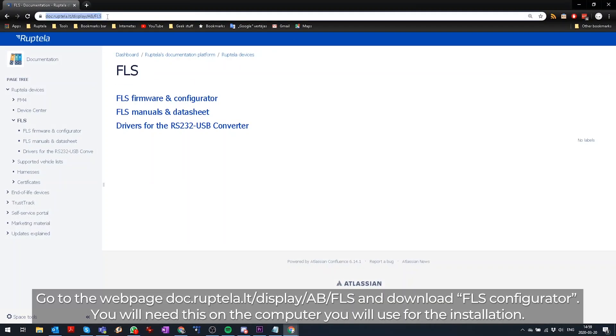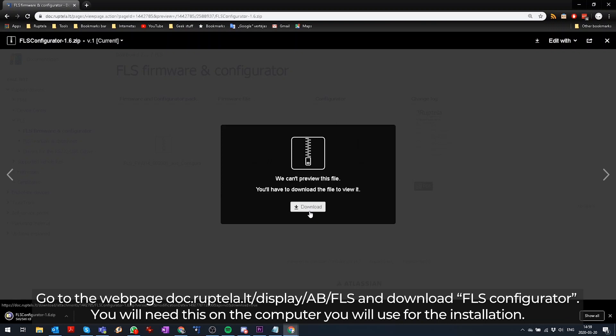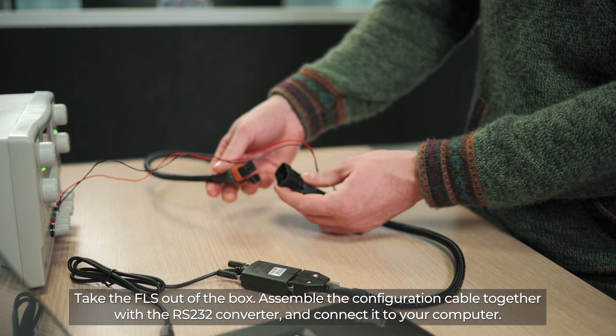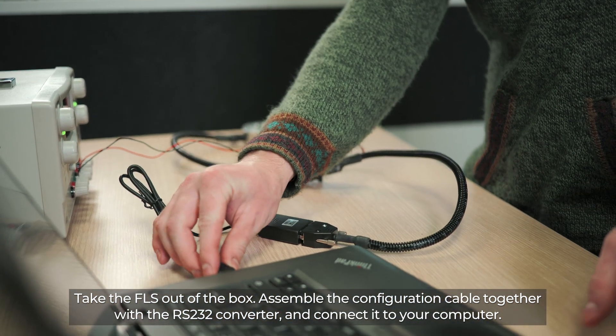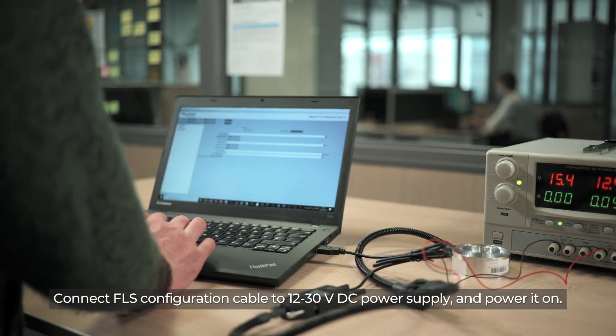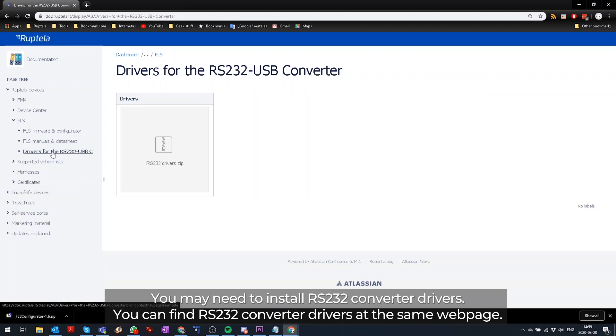Go to the webpage doc.ruptela.lt and download FLS Configurator. You will need this on the computer you will use for the installation. Take the FLS out of the box, assemble the configuration cable together with the RS232 converter and connect it to your computer. Connect the FLS configuration cable to a 12 to 30 volts DC power supply and power it on. Upon successful connection of FLS, Configurator will ask to read FLS configuration. You may need to install RS232 converter drivers.